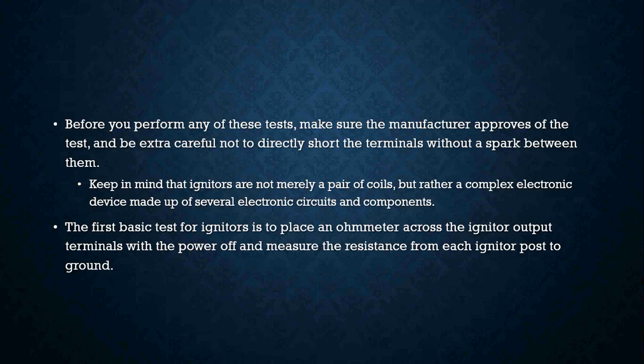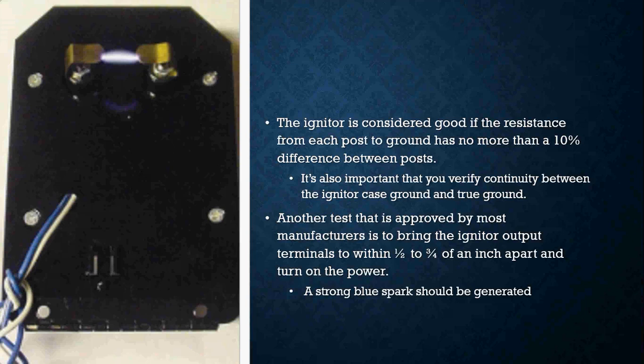Before you perform any of these tests, again, make sure that you are using manufacturer-approved testing procedures and the correct tools. And be extra careful not to directly short the terminals without a spark being between them. Okay, keep in mind that igniters are not merely a pair of coils, but rather a complex electronic device made of several electronic circuits and components. So the first basic test for igniters is to place an ohm meter across the igniter output terminals with the power off and measure the resistance from each igniter post to ground. The igniter is considered good if the resistance from each post to ground has no more than a 10% difference between the posts. Okay. It's also important that you verify continuity between the igniter case ground and true ground.